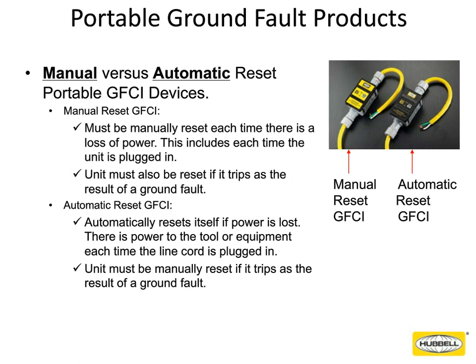An automatic reset ground fault portable will operate immediately upon plug-in. Don't be confused by an automatic reset in terms of an actual ground fault. If you have a ground fault condition and the unit does its job, whether it's a manual or an automatic, it senses a ground fault and it trips, and in both cases you must reset manually to bring power back. But a manual reset unit has to be reset every time you plug it in, and an automatic will automatically power up when you plug it in.